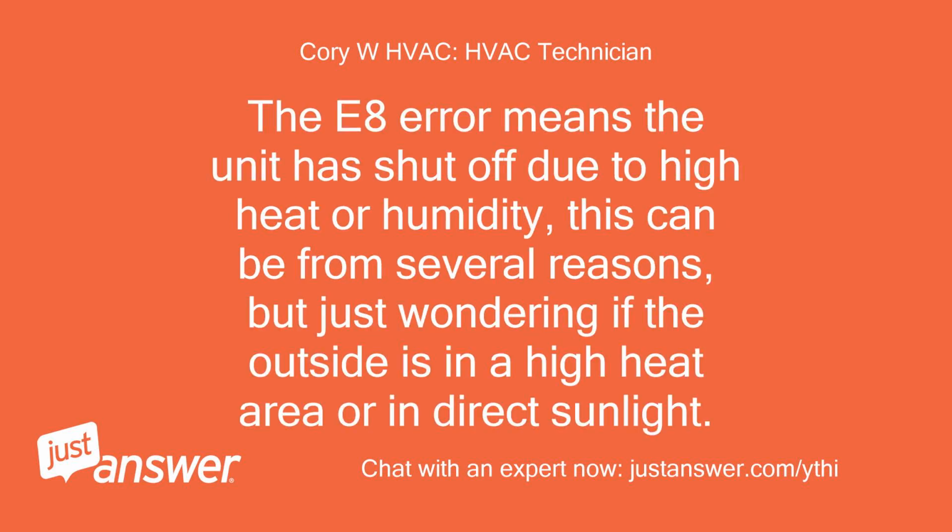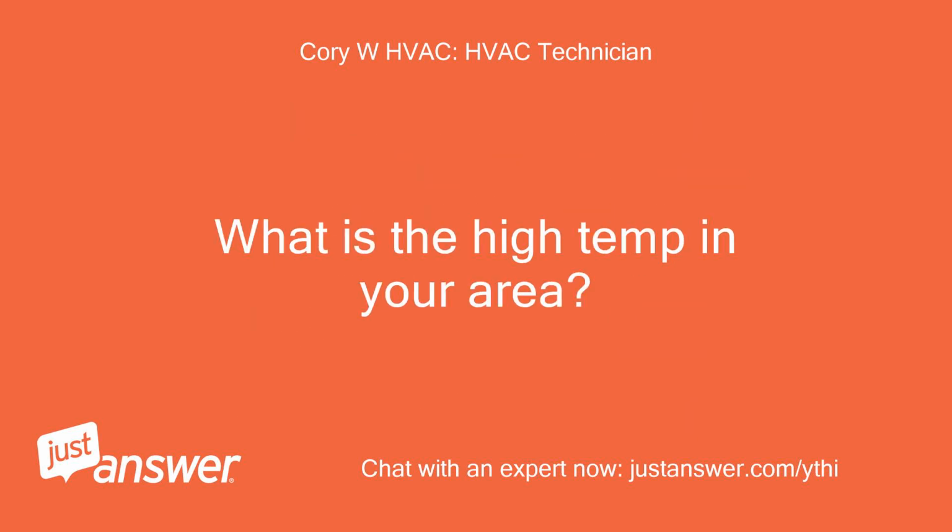The E8 error means the unit has shut off due to high heat or humidity. This can be from several reasons, but just wondering if the outside is in a high heat area or in direct sunlight. What is the high temp in your area?